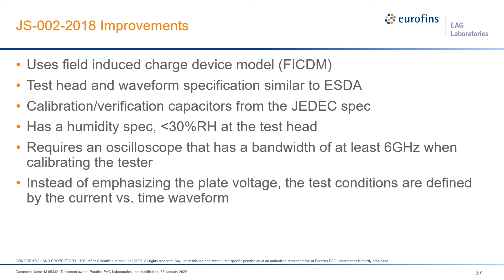So this is the JS-002 CDM waveform. The waveform on the left is the ideal one that's shown in the spec, and the one on the right is an actual waveform taken with an 8 gigahertz oscilloscope on one of our JS-002 test heads. The simplest CDM device is a capacitor. And for this waveform, we use the standard JEDEC disc capacitor, the small capacitor, 6.8 picofarads. The rise time is supposed to be less than 250 picoseconds. The real waveform shows 208 picoseconds, and it typically runs close to 200 picoseconds. The pulse width at 50% height is supposed to be 250 to 600 picoseconds.